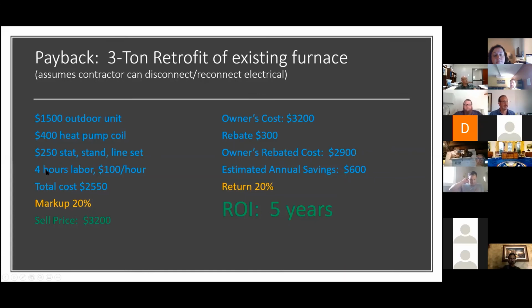So if we're looking at retrofitting a 3-ton furnace, now I have half a mind to print up flyers and go around my neighborhood and say, hey, I've got a better investment deal for you than your broker can get you. Let's look at this. $1,500, we showed this before, your outdoor unit. You're gonna need a new heat pump coil. This is a good guess for the cost, $400. We talked about the stat, raising the stand, the line set. We feel like this should be a 4-hour job, $100 an hour. If you pay your guys $100 an hour, awesome. Total cost $2,550, mark it up, $3,200 sell price.